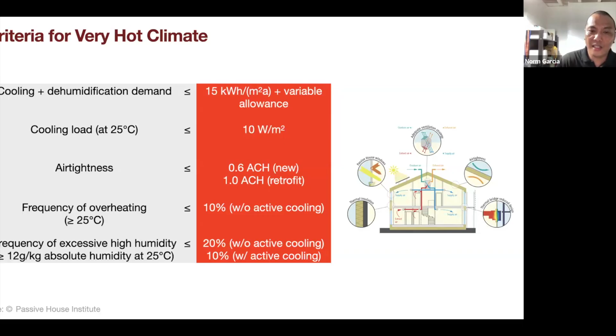And lastly, the frequency of excessive humidity, meaning the amount of water in the air greater than 12 grams of water per kilogram of air, or absolute humidity at 25 Celsius, should not be exceeded 20% of the time without active cooling, or 10% with active cooling.